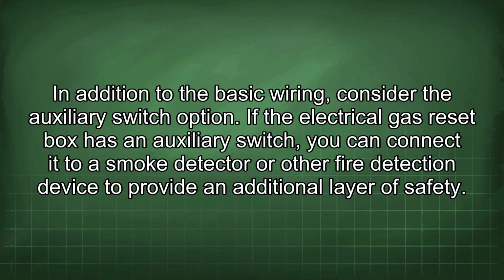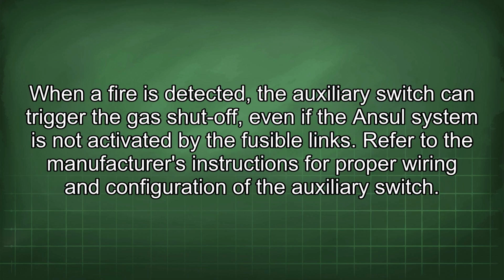In addition to the basic wiring, consider the auxiliary switch option. If the electrical gas reset box has an auxiliary switch, you can connect it to a smoke detector or fire detection device to provide an additional layer of safety. When a fire is detected, the auxiliary switch can trigger the gas shut-off, even if the Ansul system is not activated by the fusible links. Refer to the manufacturer's instructions for proper wiring and configuration of the auxiliary switch.